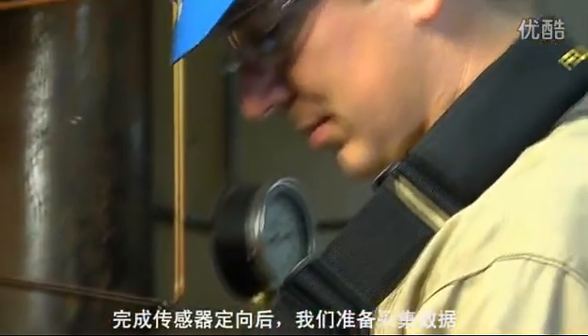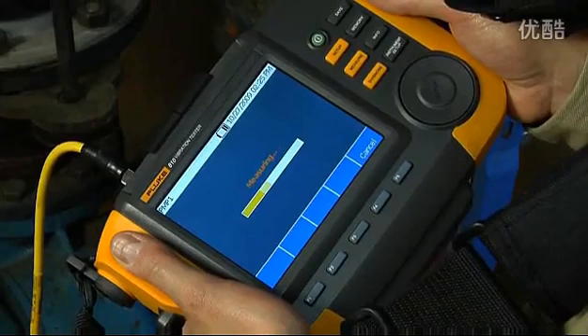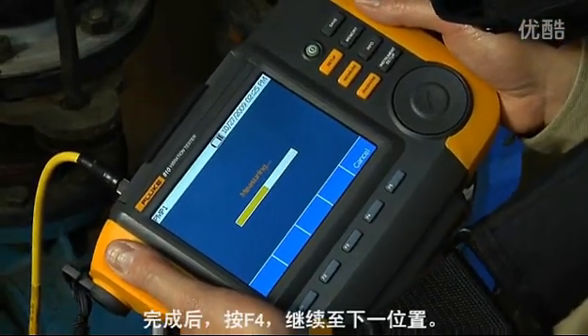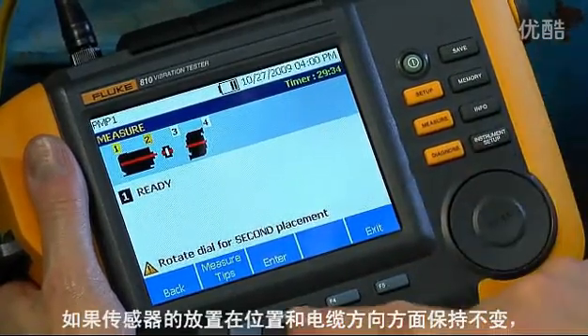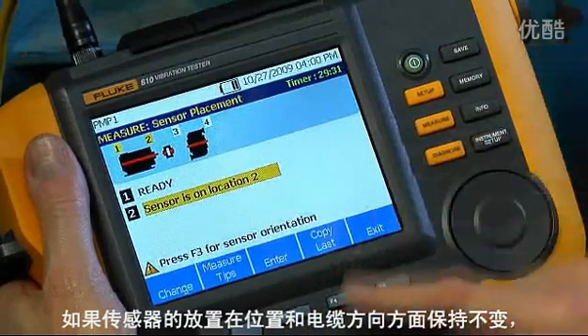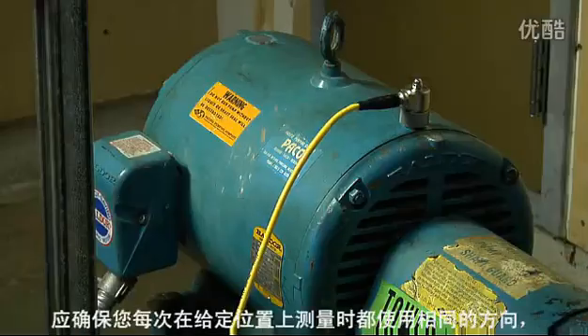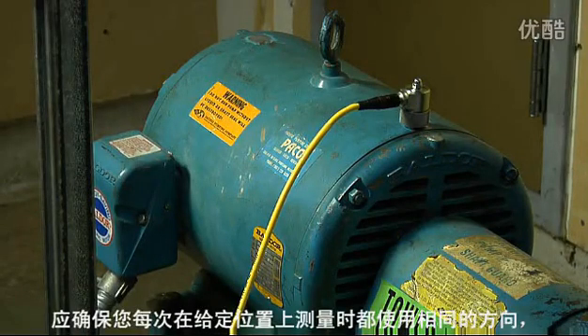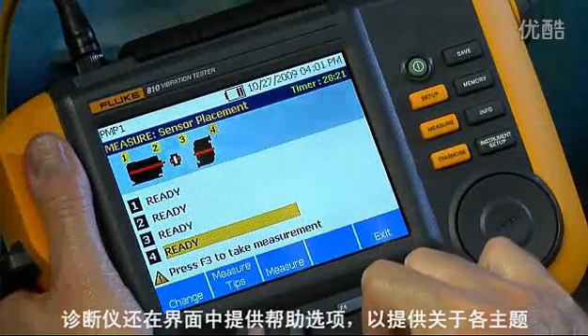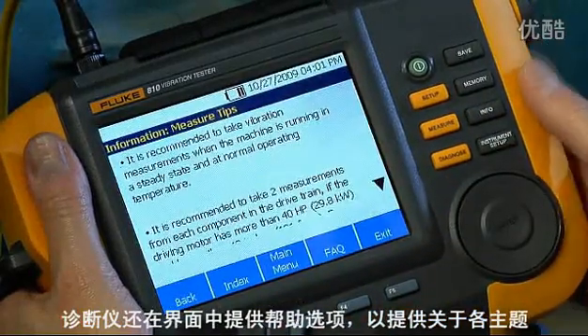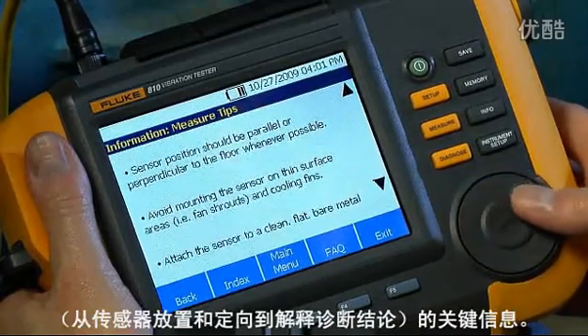Having completed the sensor orientation, we're ready to collect data. Push F3 to begin. Once that's done, push F4 to continue to the next location. If the orientation of the sensor remains the same in terms of location and cable direction, hit 'Copy Last' to use the last orientation information. It's important to use the same orientation each time you take measurements at any given location to maintain consistent diagnostic records. The tester also has onboard context-sensitive help to provide practical information on sensor placement, orientation, and interpreting the diagnostic output.